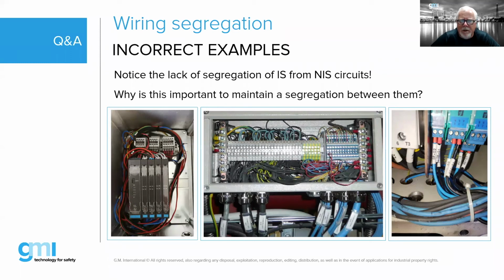And that picture in the middle, again, when it came out from the factory, we had our blue terminals on the right-hand side, segregation. Our power terminals, looks like there was an earthing plate. There was also some earth terminals, which is separate. So probably one of those was our PE. One of those could have been just our clean earth. I'm not really sure which is which, but obviously it's all jumbled up, and we've missed out on our 50 mil separation.